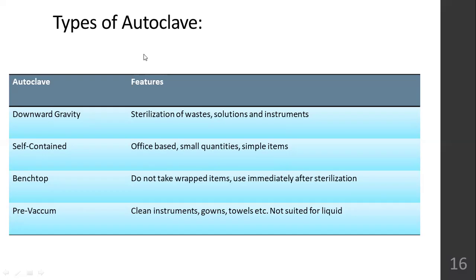Okay, so in OT, emergency department, ICUs, they can use benchtop sterilizers. You don't have to waste time wrapping it, but it will give you sterilization. Immediately you have to use the instrument. You can't keep it for future use. And pre-vacuum cannot sterilize any liquid, but gowns, towels, clean instruments, for that, pre-vacuum sterilizer or autoclave can be used.